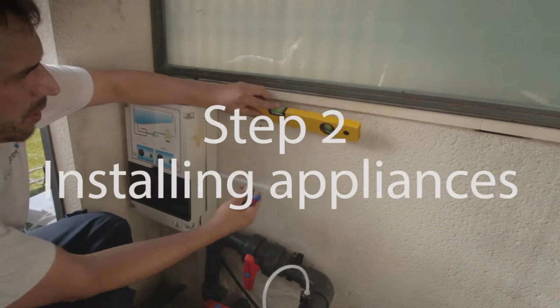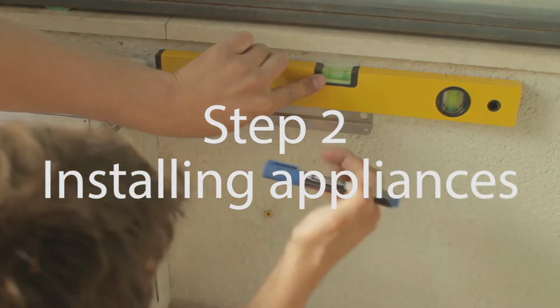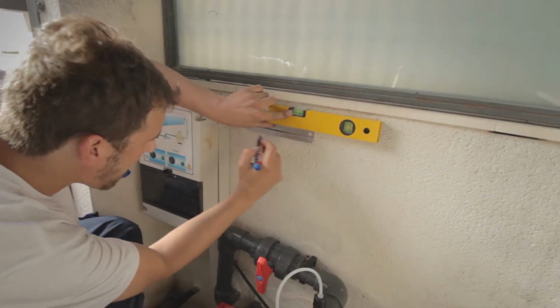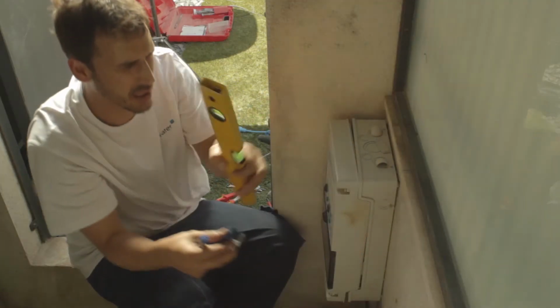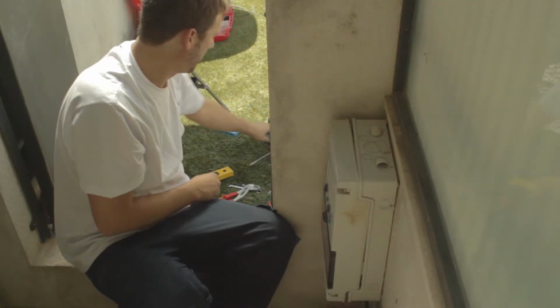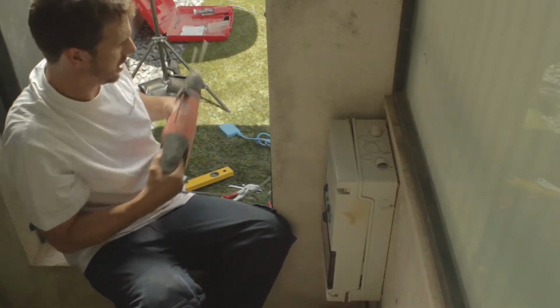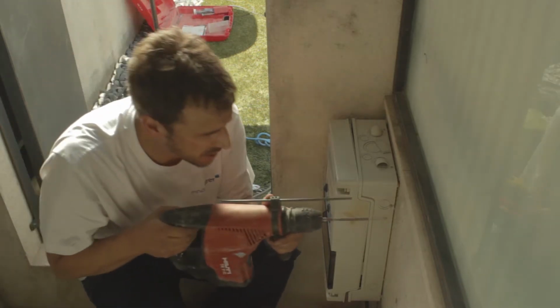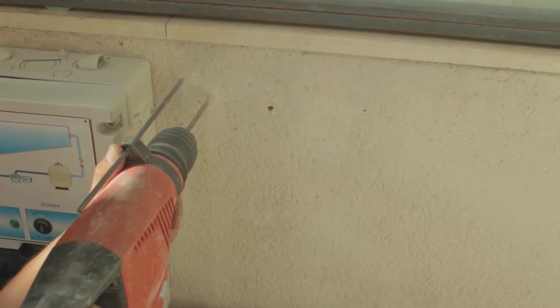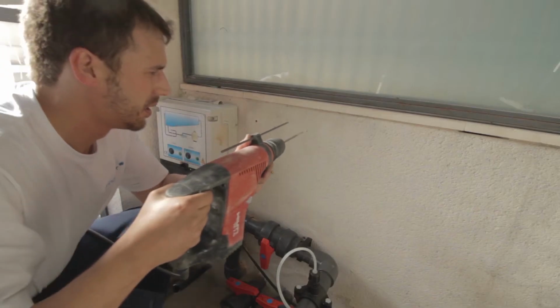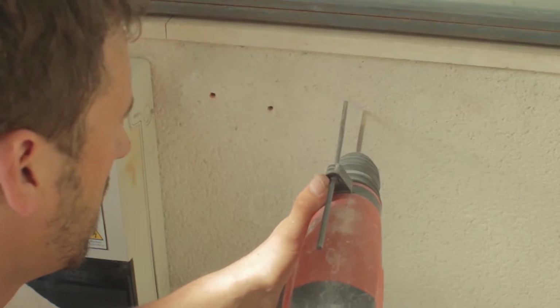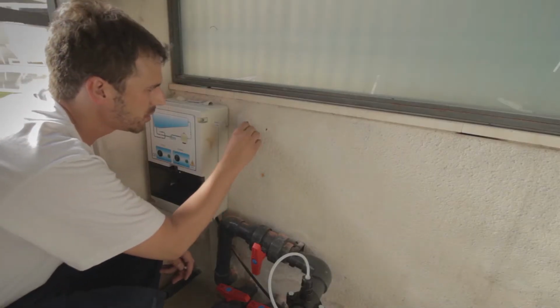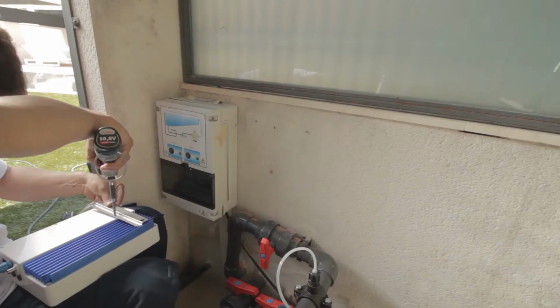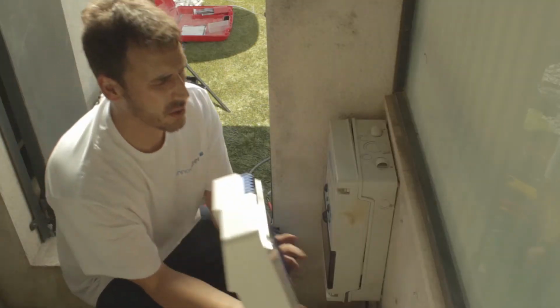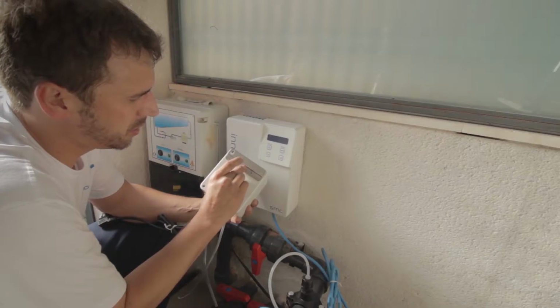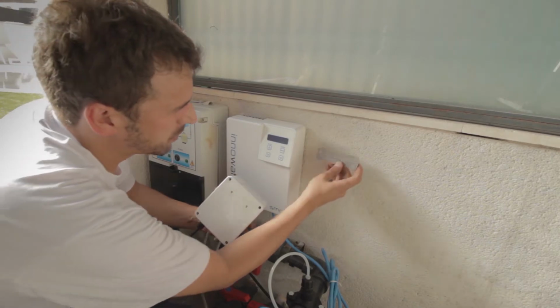Step 2. Installing appliances. To install the chlorinator and the regulator, we use loose brackets to facilitate the installation. Fix the brackets using a level, adjusting and marking to enable subsequent drilling with a size 6 bit. Fix the dowels and screws that come with the equipment. It's much easier to fix the chlorinator in hanging position. We do the same with the mount for the pH regulator.